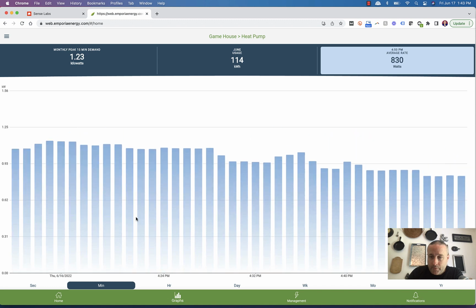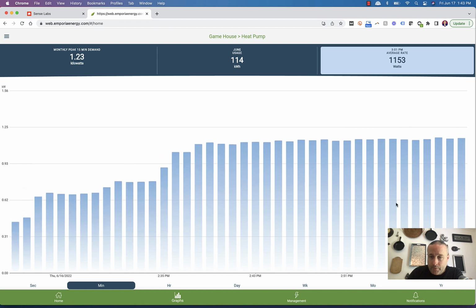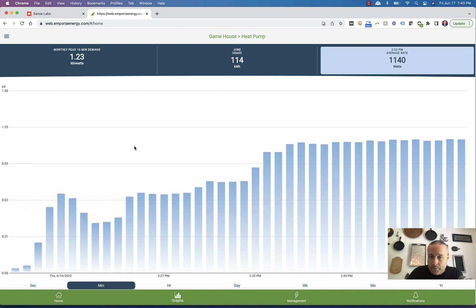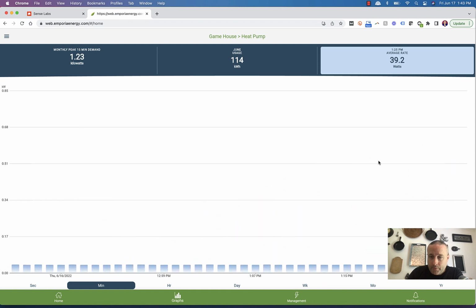Well, let's get back into the heat of the day yesterday. So it was running along. I think this unit is basically limited at a ton or thereabouts. So there's 1,230. Interestingly, its wattage consumption is pretty similar to the 2-ton here, but it can't go as high. And then it has a boost mode, which lets it into more capacity when you get to a certain temperature. We should have been there yesterday, but it didn't need that capacity, or it would have used it. So here we're off for a pretty good while.